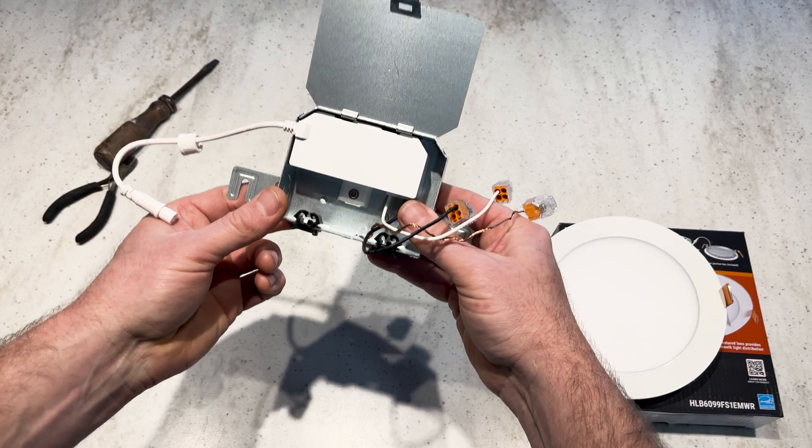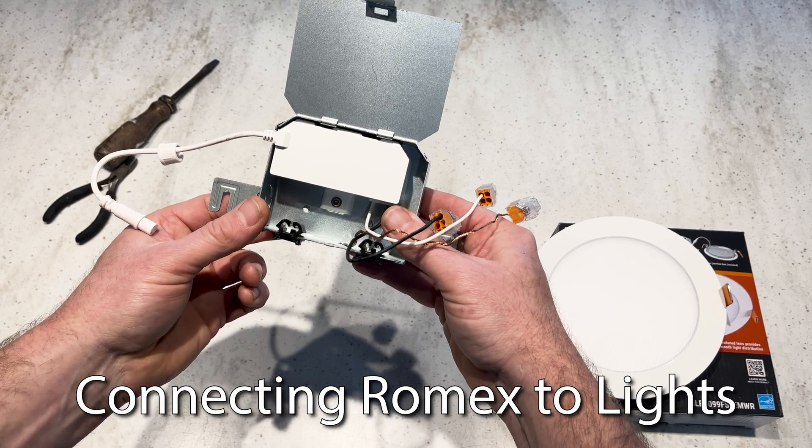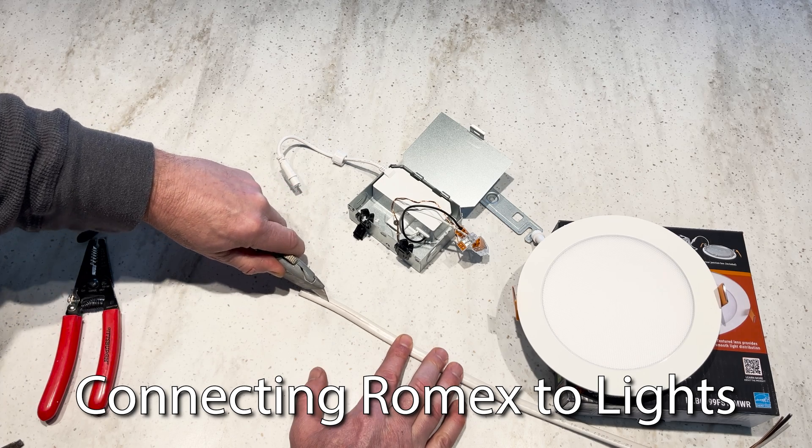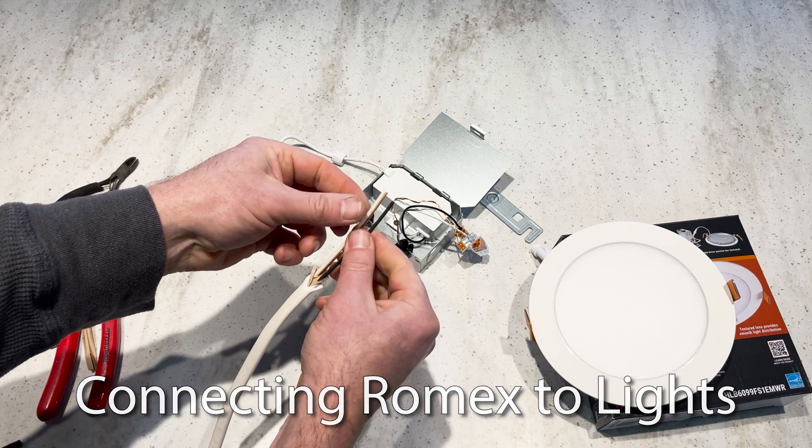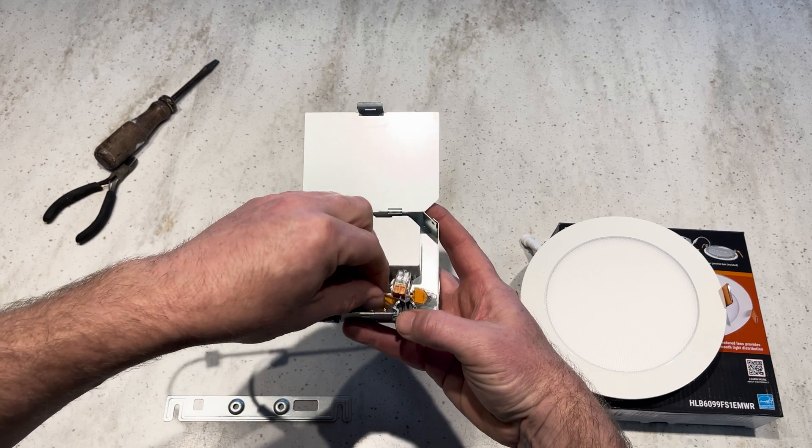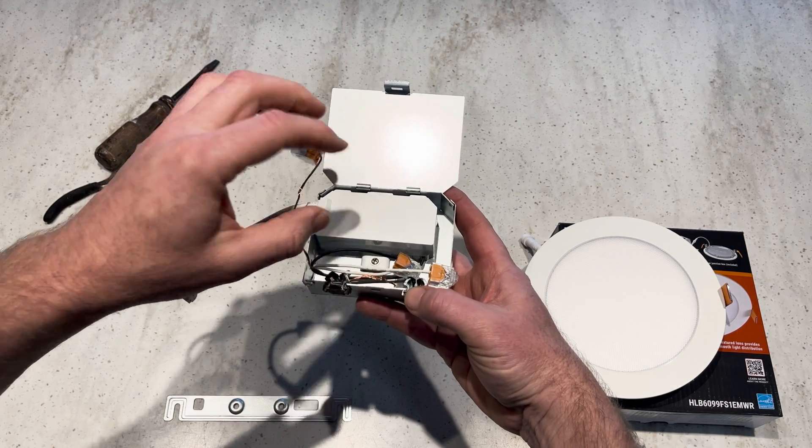Finally, it's time to connect my Romex to my lights. This is a canless six inch light by Halo and it's pretty slick. I strip a few inches of the protective outer jacket off of the Romex to expose the black, white, and ground wires and pop open the junction box to connect them to wires of the same color coming from the light.